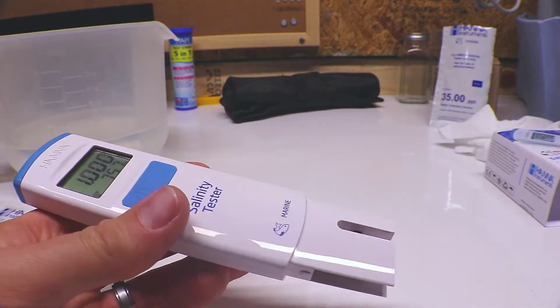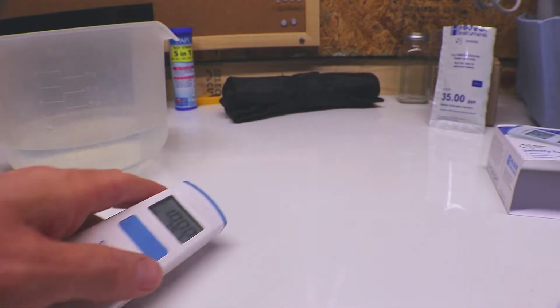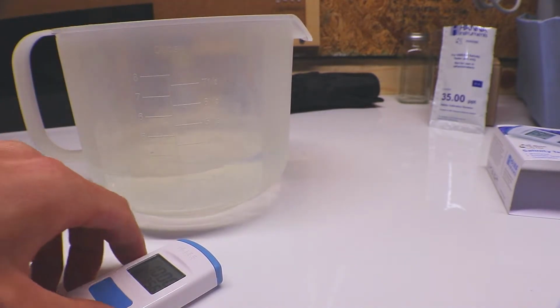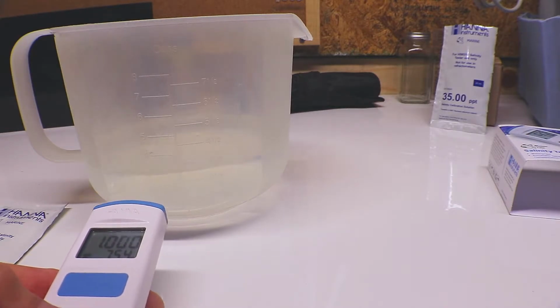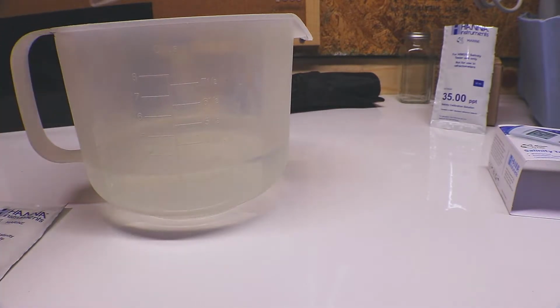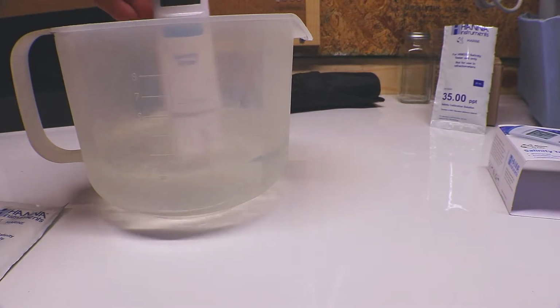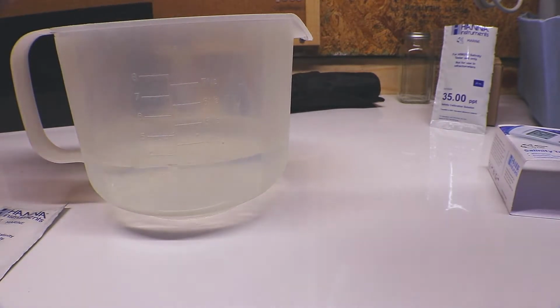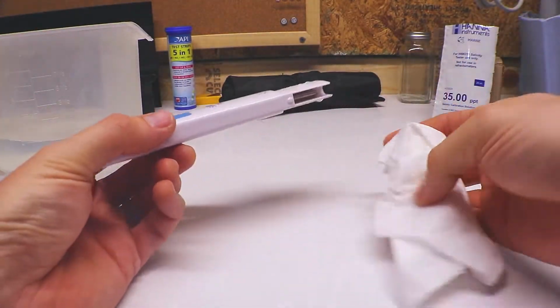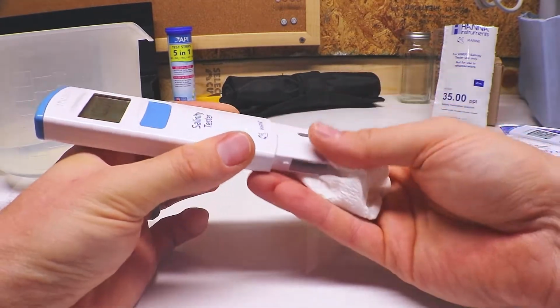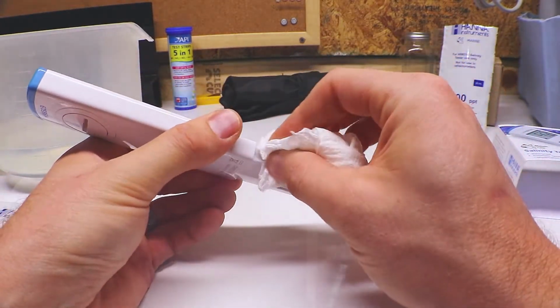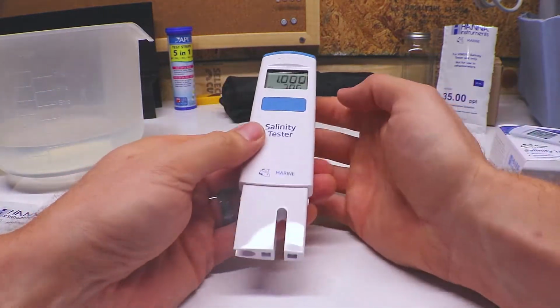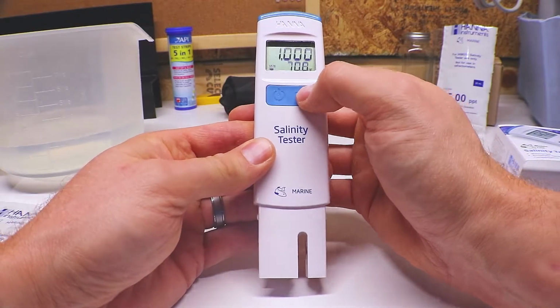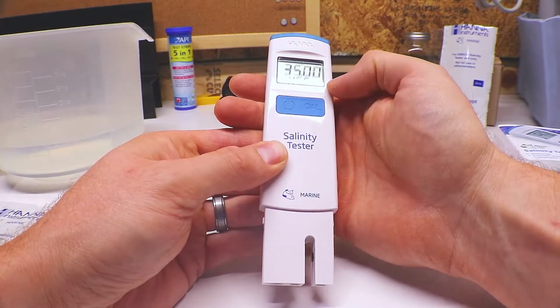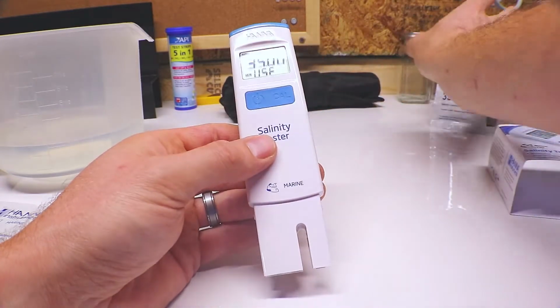So to calibrate this, what it says to do, first get a paper towel, and then in this cup, I've got RODI water. It says to use RODI water or purified water, and you want to dip the probe in, give it a few swirls. This is to rinse off the probes. After you rinse, it says to dry them off with a clean paper towel. After you do that, you hit the calibration button, and on the screen it'll show calibrate. Calibrate's blinking and it's ready to calibrate.